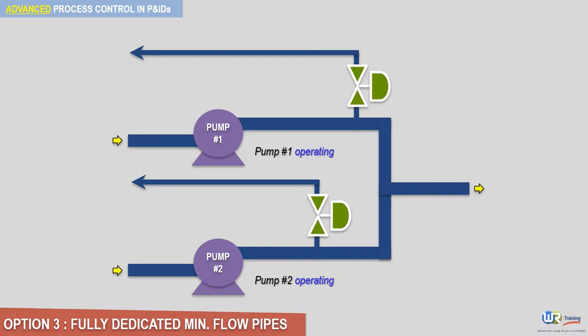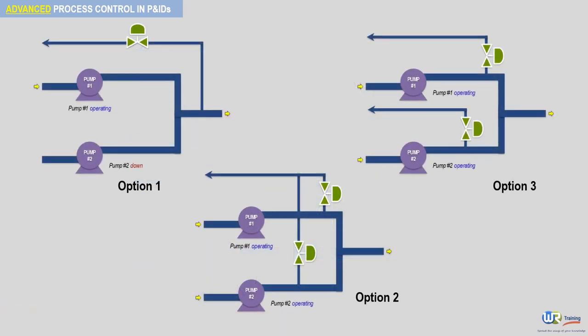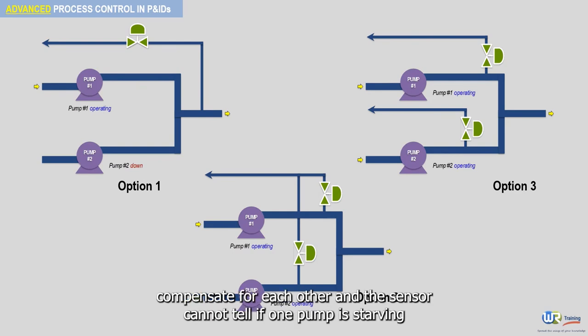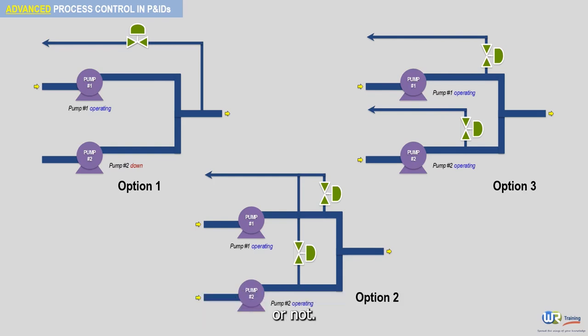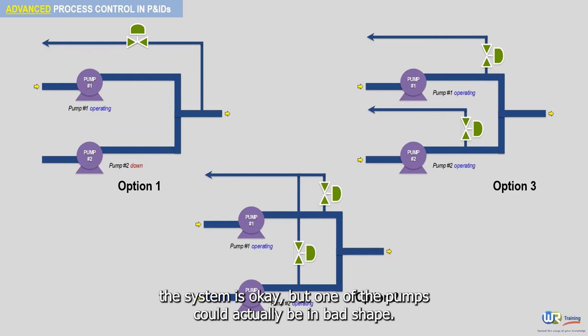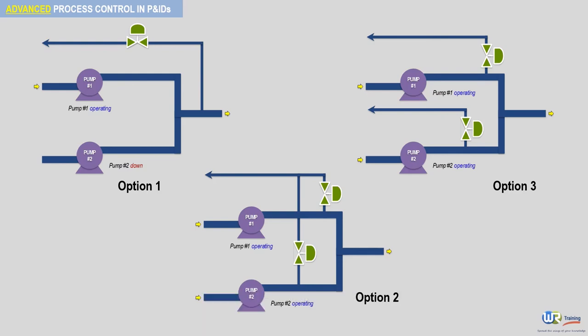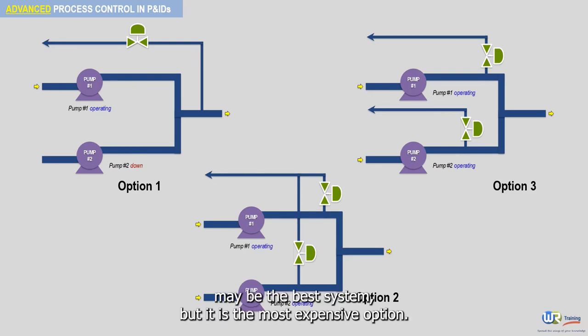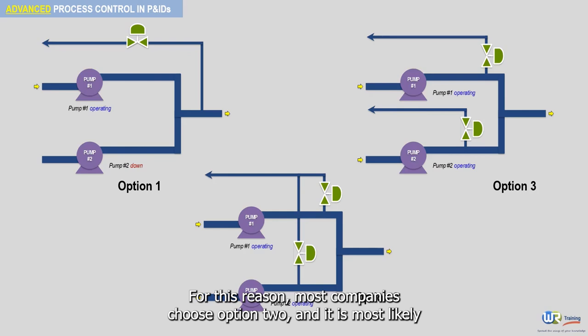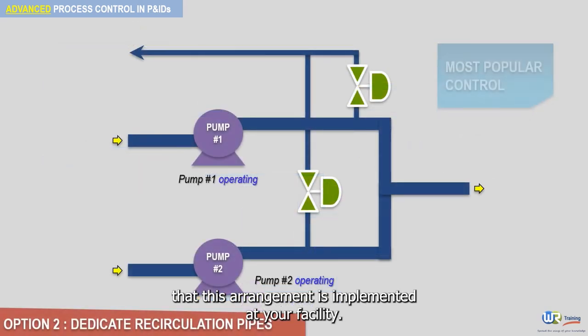The problem with option 1 is that the flow from the two pumps compensates for each other, and the sensor cannot tell if one pump is starving or not. The sensor could be telling you that the system is okay, but one of the pumps could actually be in bad shape. Option 3 may be the best system, but it is the most expensive option. For this reason, most companies choose option 2, and it is most likely that this arrangement is implemented at your facility.